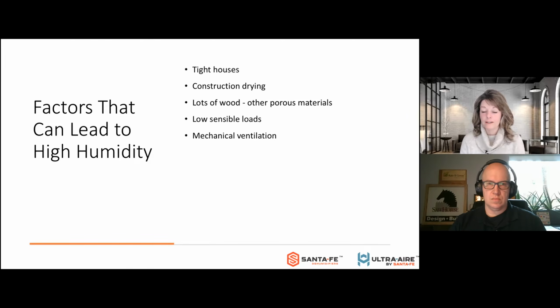And then mechanical ventilation. We've got to do it. It's code. It should be being measured. We can talk about different ventilation strategies, but the reality is if there are people in the home, we should be ventilating in order to dilute and minimize indoor air contaminants. So mechanical ventilation, if you are bringing in the outdoor air in a mixed humid climate in the spring, summer, or fall, you are bringing in moisture, and it's going to have to be dealt with.